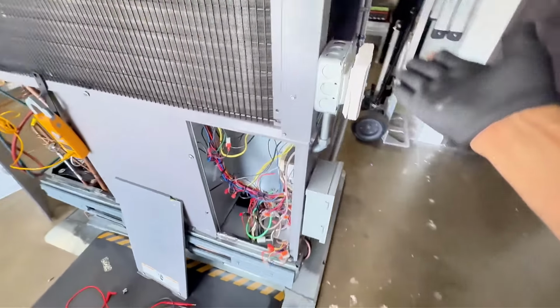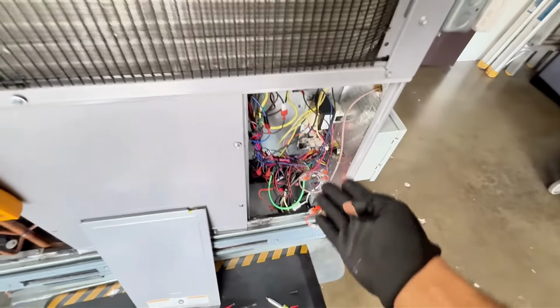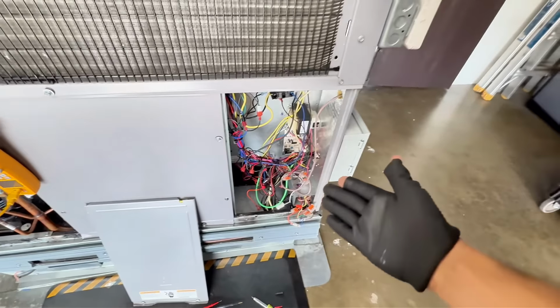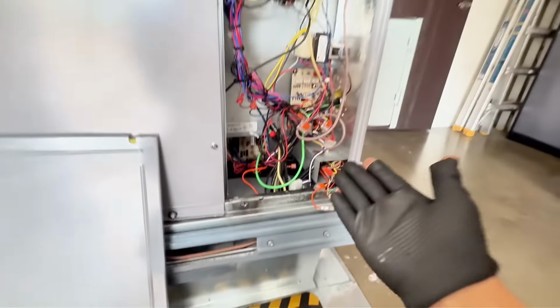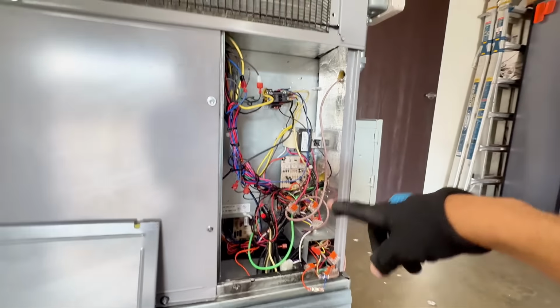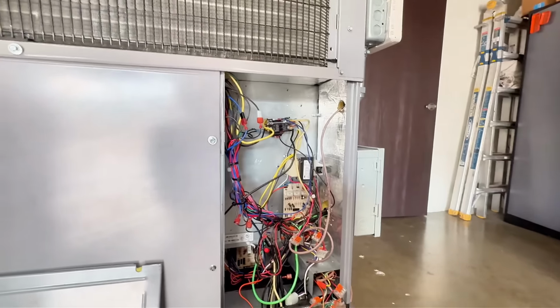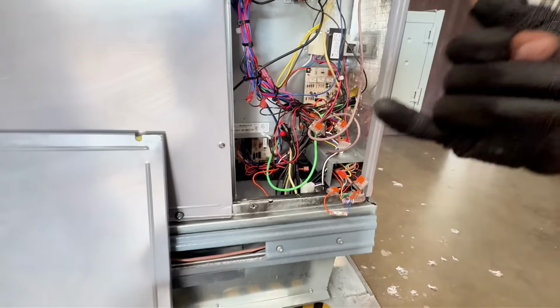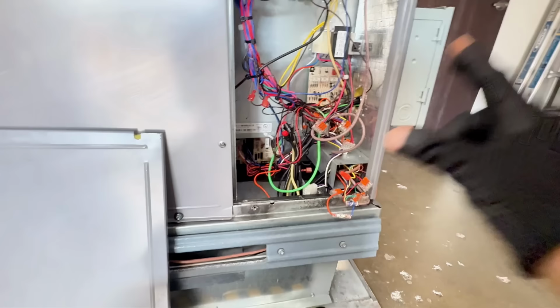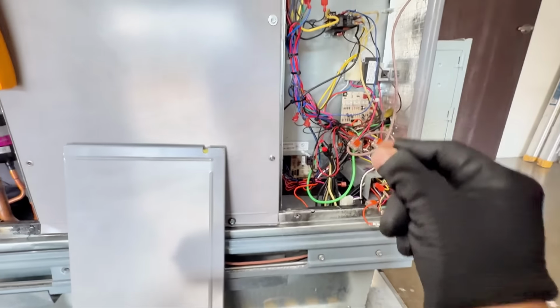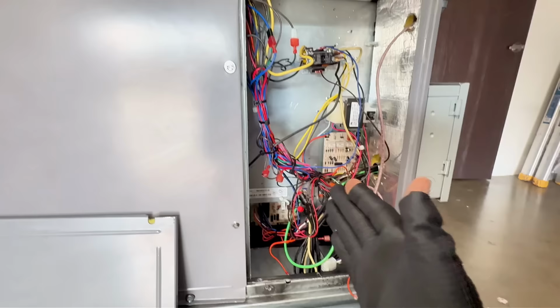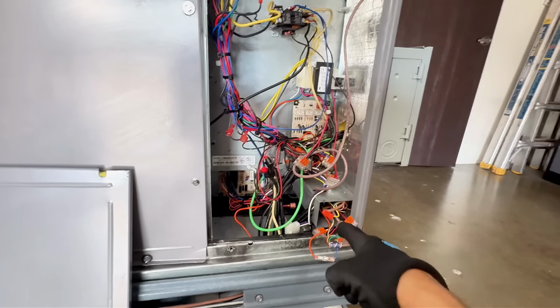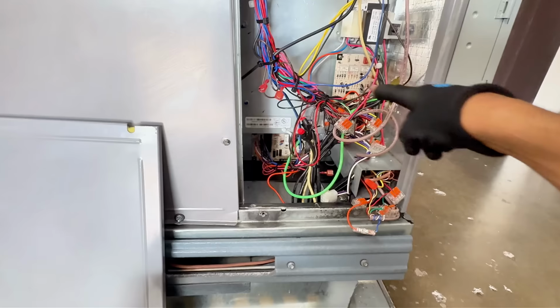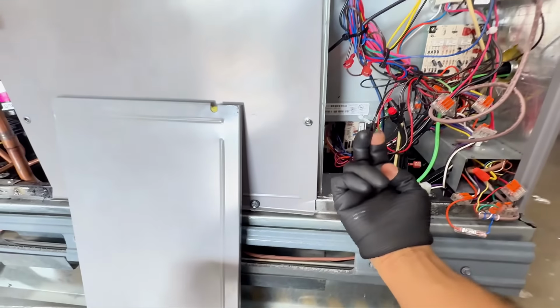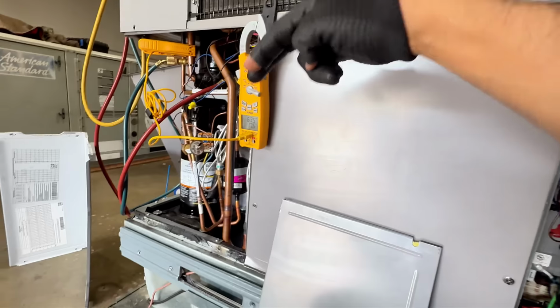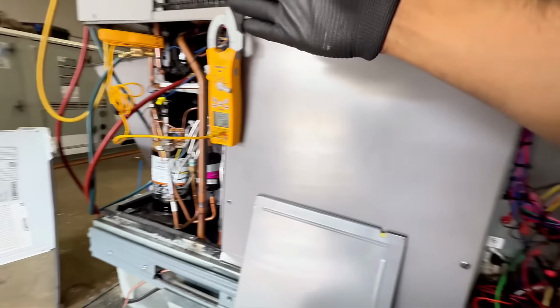So now you come here, you call for cooling. Boom. Between Y and C, it should be 24 volts. And if you're not getting 24 volts between Y and C, something's going on with the wiring, or maybe the light works, but it could be a bad thermostat head. So you saw me checking 24 volts between Y and C and O and C. After that, it is important to understand, once again, the path that 24 volts takes. Once I send 24 volts to Y, the 24 volts travels to this board right here, and then it comes out through my pressure switches, power in, power out, power in, power out, and then it comes back to the board.